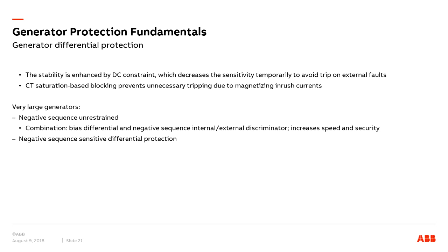So we need to deal with some of the inherent problems in the electrical system when we design the differential protection scheme. One is dealing with the DC constraint, and there is a possibility of enhancing the stability for DC constraint with a DC constraint setting, which decreases the sensitivity temporarily to avoid trip on external faults. And there's a possibility of CT saturation based blocking, preventing unnecessary tripping due to magnetizing inrush current. So when you have an inrush current situation, that could be a CT saturation.